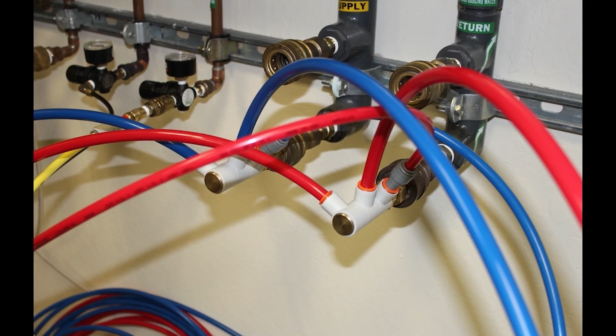But as the lasing medium needs to be cooled continuously to laze, cool water is continuously pumped to the laser. So, if there is a water leakage inside, or anywhere near the laser system, it creates the perfect situation for an electrical hazard. So, if there is any water leakage inside the cavity or near the laser or power supply, turn off the electricity immediately by pressing the emergency stop button.